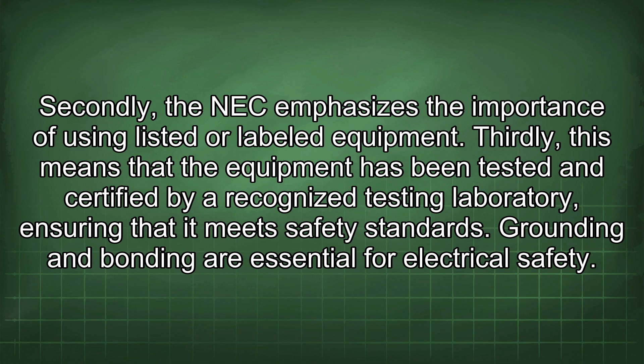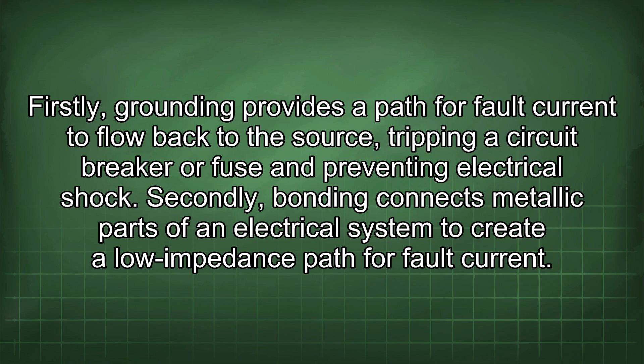Grounding and bonding are essential for electrical safety. Grounding provides a path for fault current to flow back to the source, tripping a circuit breaker or fuse and preventing an electrical shock. Bonding connects metallic parts of an electrical system to create a low impedance path for fault current.